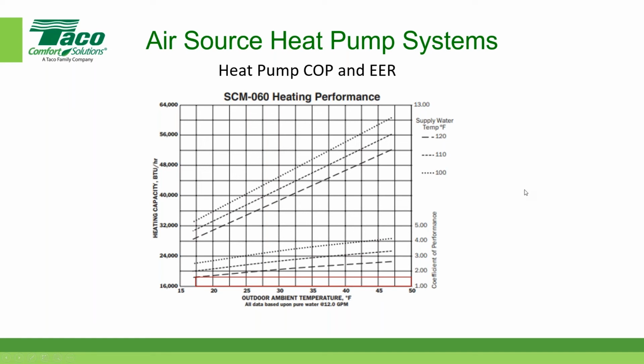Dan made a good point. The best design is to keep your supply water as low as possible, as long as it can heat your house. Exactly. So when you're starting to think about these types of systems, you have to think about what the terminal devices look like. And certainly 100 degrees is more than enough temperature if you had a radiant floor heating system.